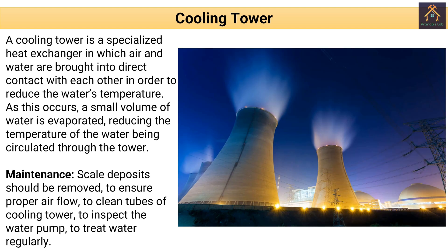Next, the cooling tower. A cooling tower is a specialized heat exchanger in which air and water are brought into direct contact with each other in order to reduce the water's temperature. As this occurs, a small volume of the water is evaporated, reducing the temperature of the water being circulated through the tower. The maintenance of the cooling tower is done by removing scale deposits to ensure proper air flow, cleaning the tubes of the cooling tower, inspecting the water pump, and treating the water regularly.